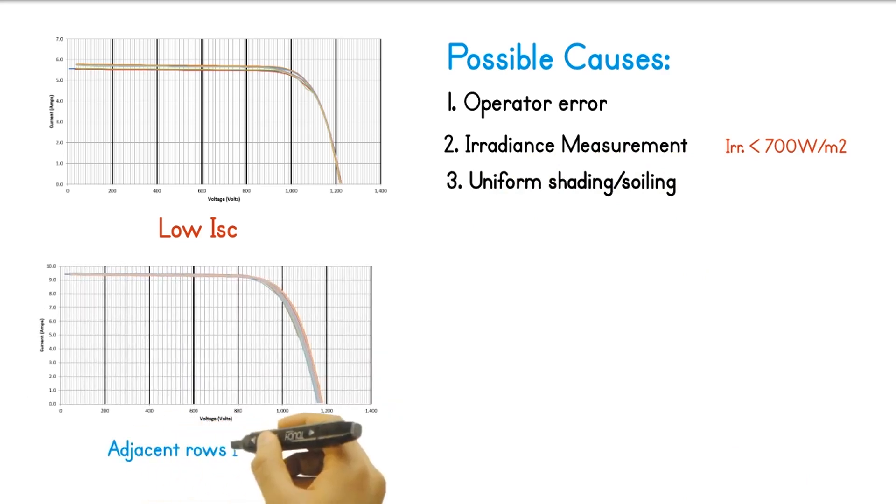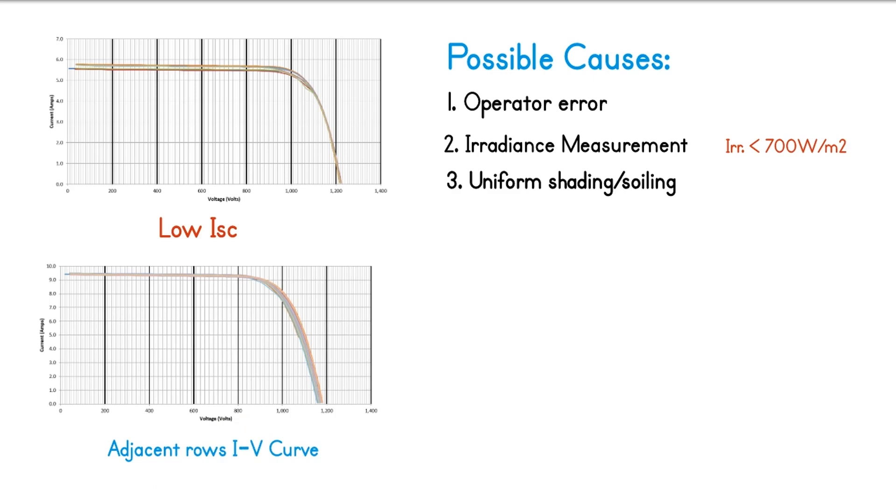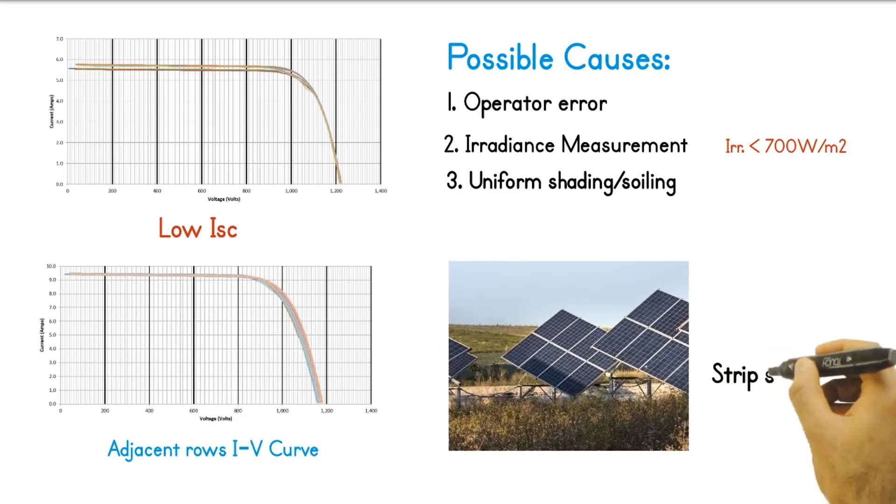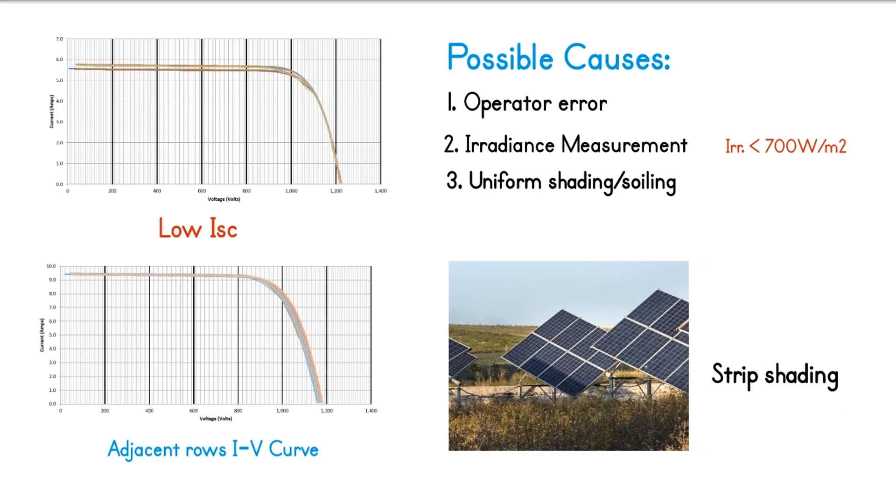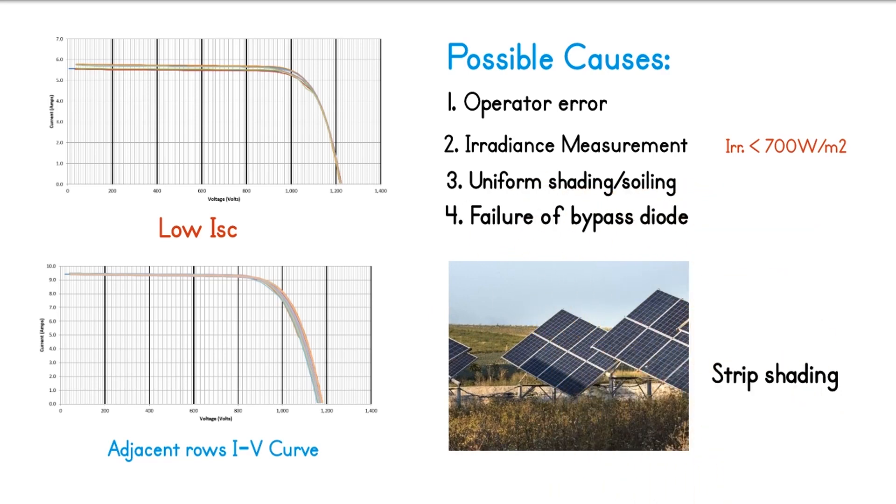When the ISC is relatively lower than that of the strings from the adjacent arrays, check if there is uniform soiling on the PV modules. Clean and retest. Also, make sure that there is no strip shading, which is common to tilt up arrays with closely spaced rows. Failure of bypass diode on the PV modules is also a cause of low ISC.